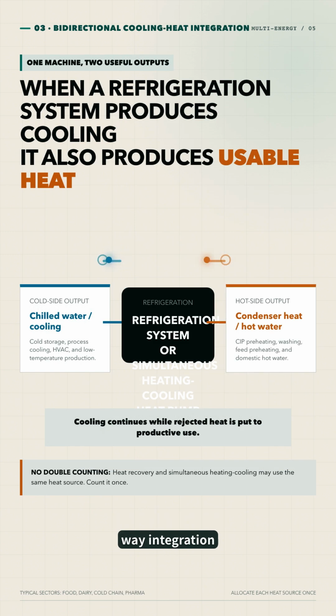The third type is two-way integration between cooling and heating. A refrigeration system does not only produce cooling, it rejects heat at the same time. Cold stores, dairy plants, beverage and brewery operations, food processors, and pharmaceutical factories may use condenser heat for domestic hot water, cleaning water, CIP preheating, feed preheating, or low-temperature process heat. Where cooling and heating are required simultaneously, a heat recovery chiller can supply cooling on one side and useful heat on the other. In the reverse direction, high-temperature steam, flue gas, or process waste heat can drive absorption cooling. The most common mistake is double counting the value of condenser heat recovery and a heat recovery chiller. They may use the same heat source. Only one constrained, technically feasible configuration can remain in the final business case.